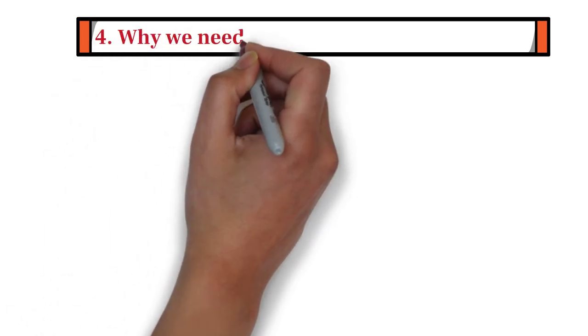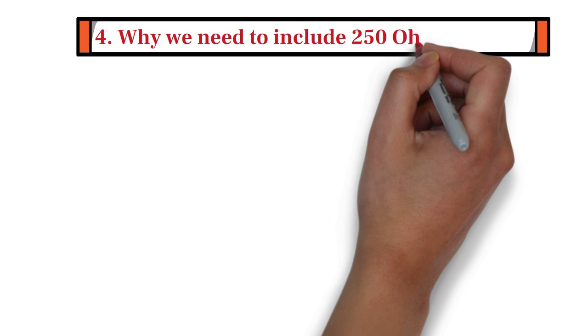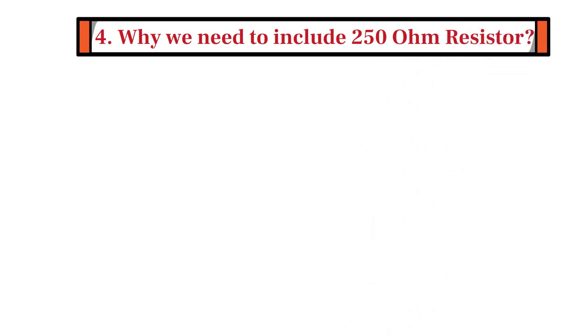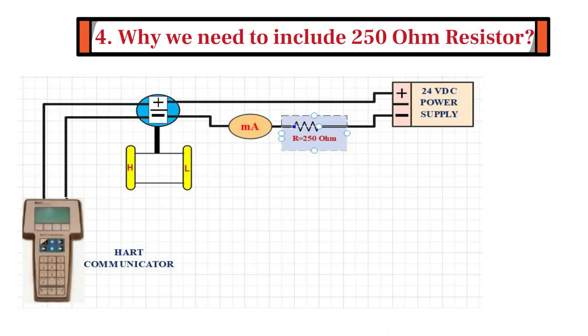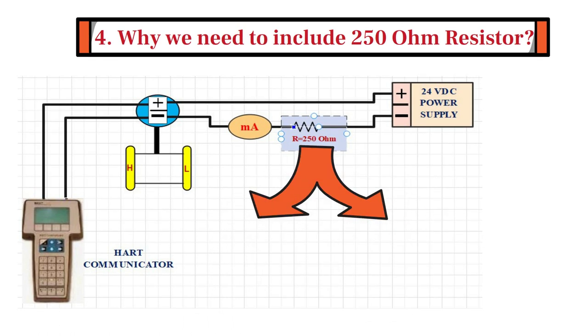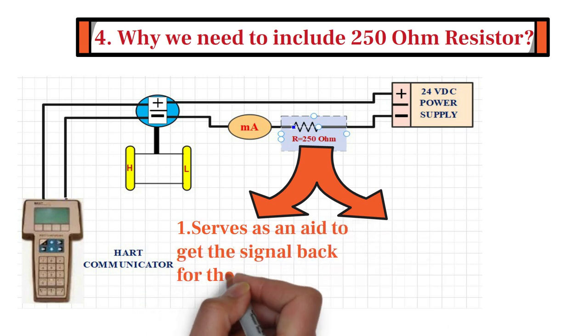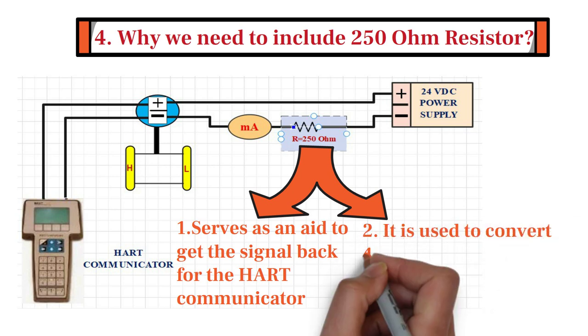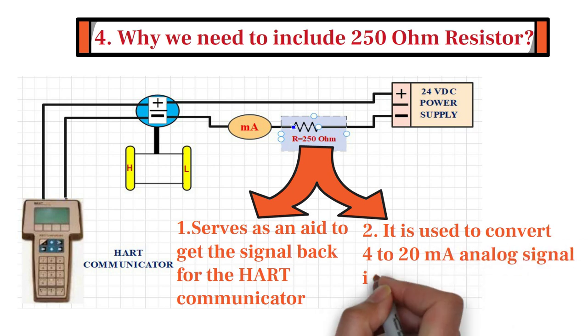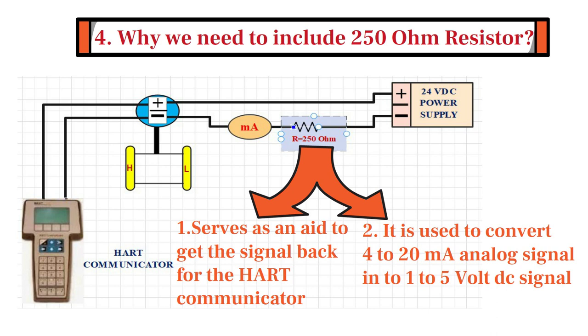Fourth and the most important question is, why do we need to include 250-ohm resistor in the loop while using HART protocol? There are mainly two reasons to include 250-ohm resistor in the loop. Firstly, 250-ohm resistor serves as an aid to get the signal back for the HART communicator. And secondly, 250-ohm resistor is also used to convert 4-20 mA analog signal into 1-5-volt DC signal, which is required for DCS and PLC.